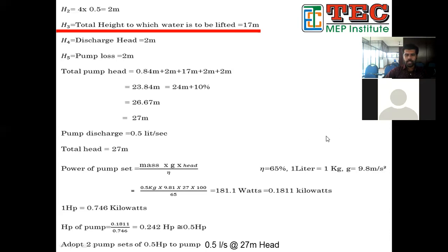So today we have found out the overhead tank capacity according to the water demand by individual people, according to the application or category. And we can take from the MDC chart how much, 100 liter per day or 90 liter per day or 20 liter per day, like that. Then we have found underground tank capacity. We have taken 2 to 3 days storage of the overhead tank. Then we have found out the main pipe size, the pumping main size, which means the water that you are pumping from the underground tank to the overhead tank, that you can find by the help of a formula.